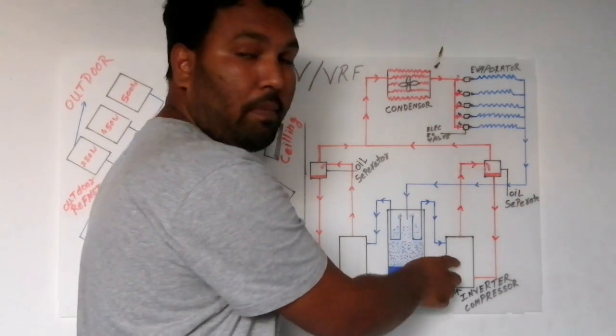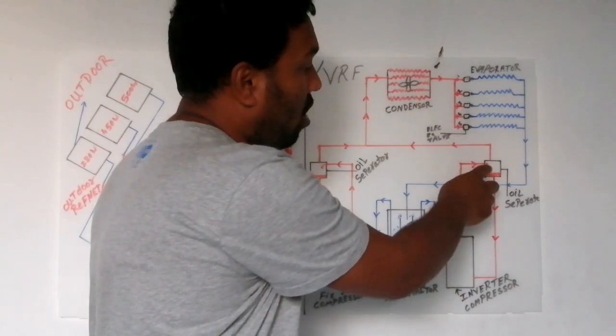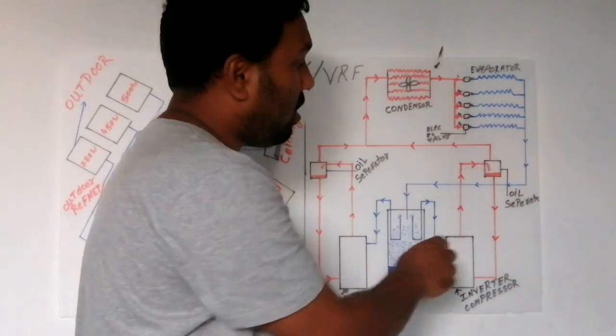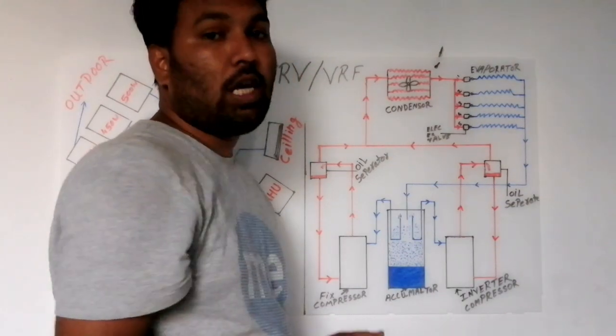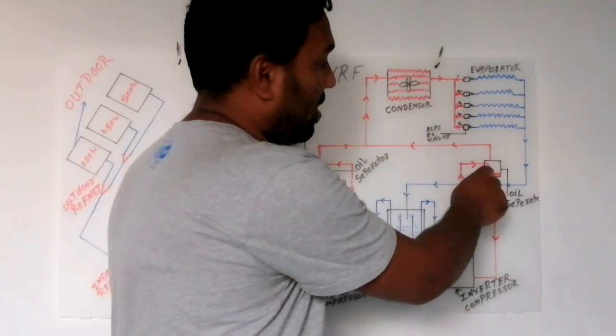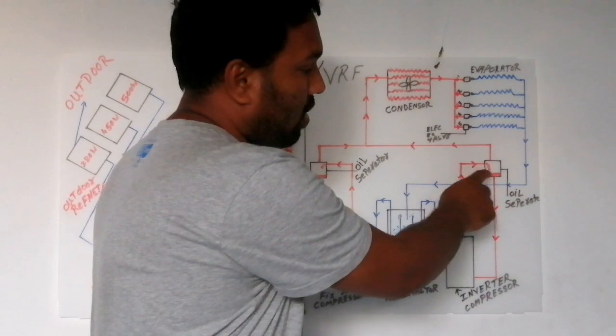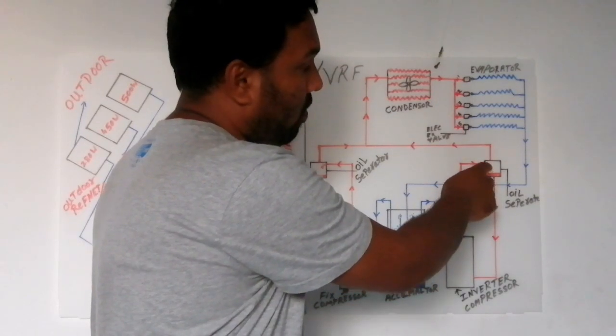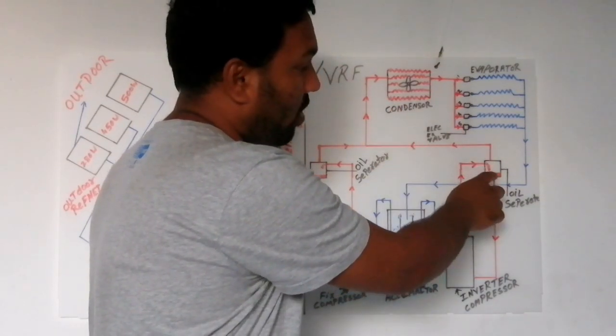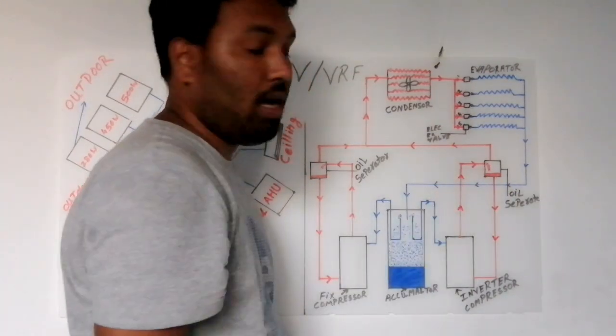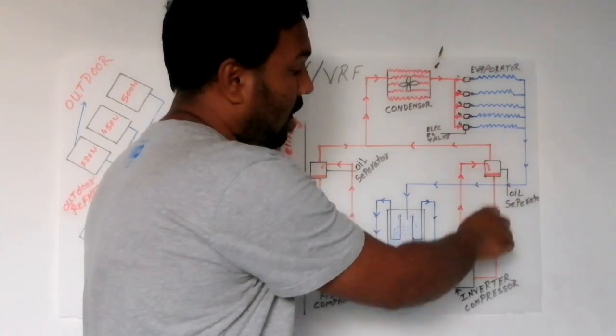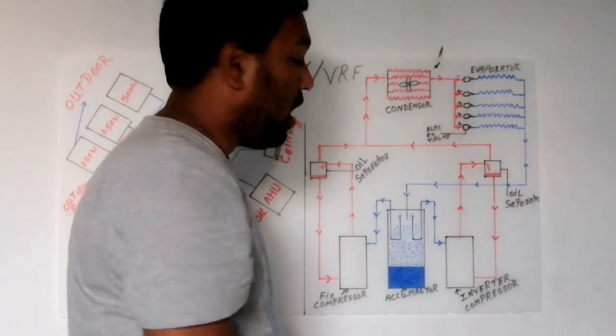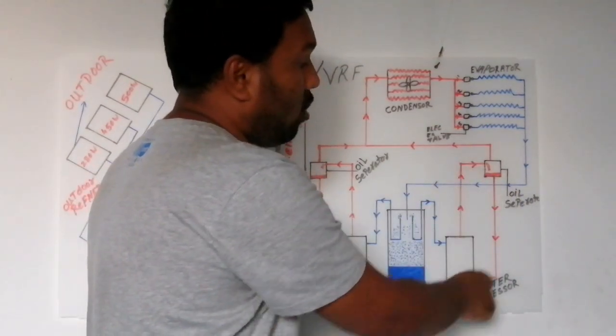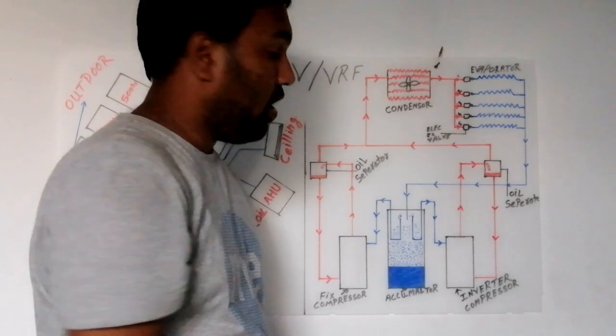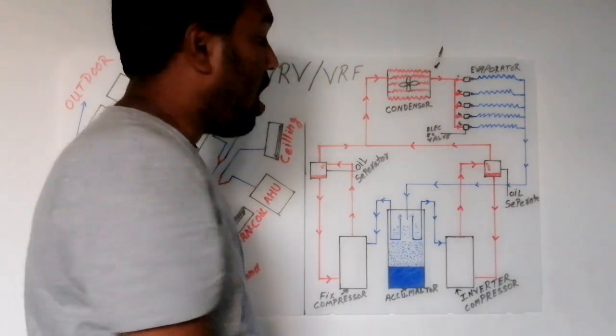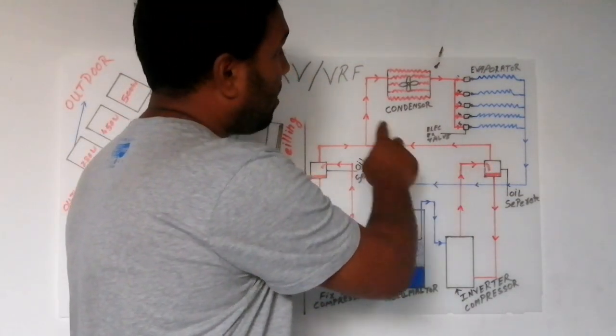From here, when our compressor pushes the refrigerant, it goes to the oil separator. In the oil separator, if the refrigerant carries some of the oil of the compressor, it gets settled at the bottom. The vapor form goes to the condenser coil, and the liquid form settles down in the oil separator. And this liquid again comes back to our compressor. It means the oil separator balances the lubricant of our inverter or fixed compressor. And after the oil separator, it comes to the condenser coil.